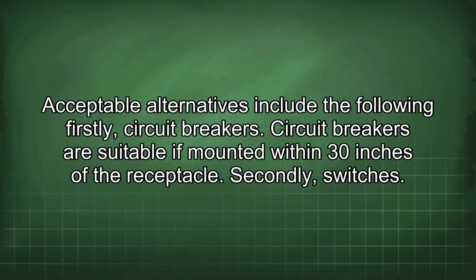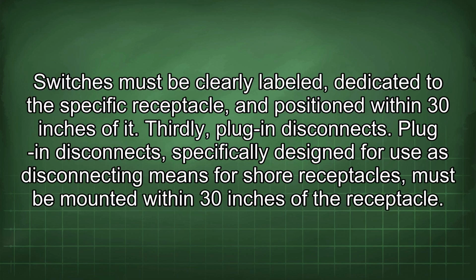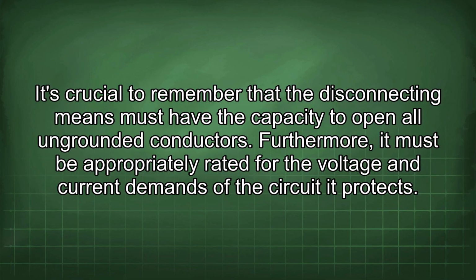Firstly, circuit breakers. Circuit breakers are suitable if mounted within 30 inches of the receptacle. Secondly, switches. Switches must be clearly labeled, dedicated to the specific receptacle, and positioned within 30 inches of it. Thirdly, plug-in disconnects. Plug-in disconnects, specifically designed for use as disconnecting means for shore receptacles, must be mounted within 30 inches of the receptacle. It's crucial to remember that the disconnecting means must have the capacity to open all ungrounded conductors. Furthermore, it must be appropriately rated for the voltage and current demands of the circuit it protects.